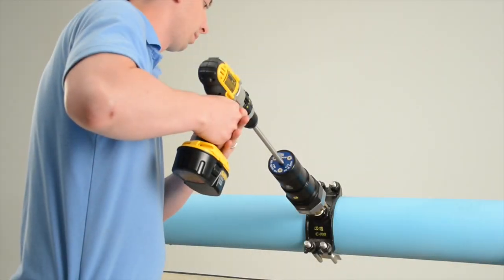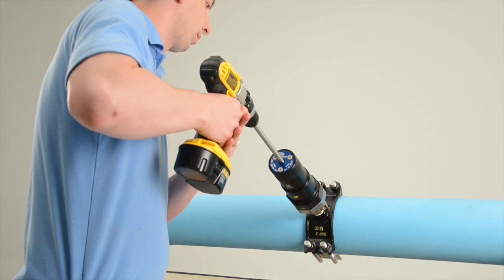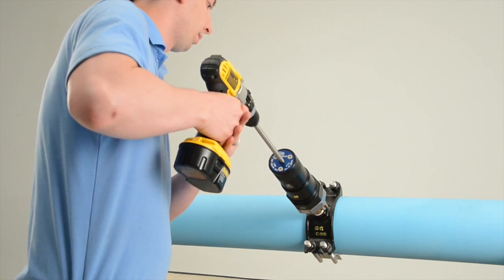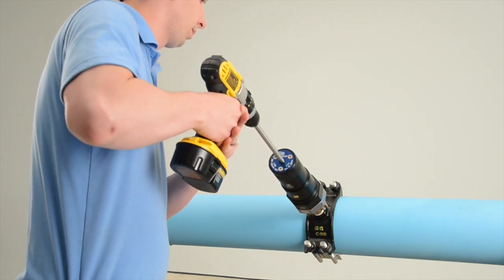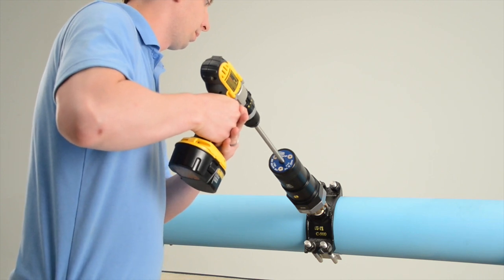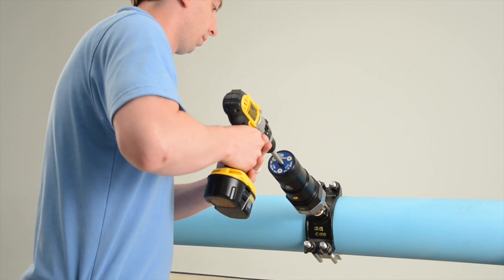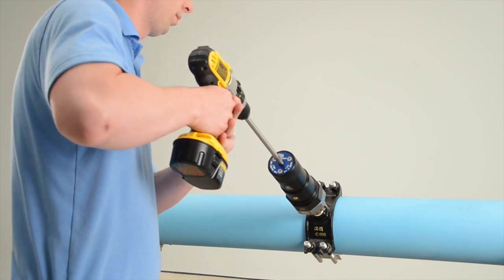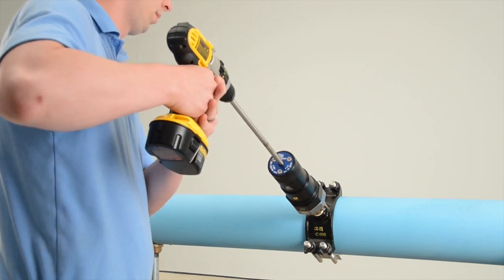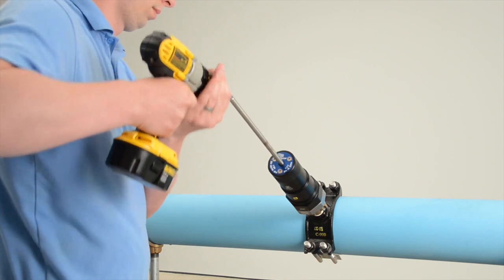During the cut, you should apply steady pressure on the pipe. When the cutter penetrates the pipe, the resistance will change and you will feel the SimTap completing the tap. It is very important to remember that when you start the tap, not to stop drilling until the tap is complete and you have pulled the saw or cutter from the pipe and it bottoms out inside the body of the SimTap.